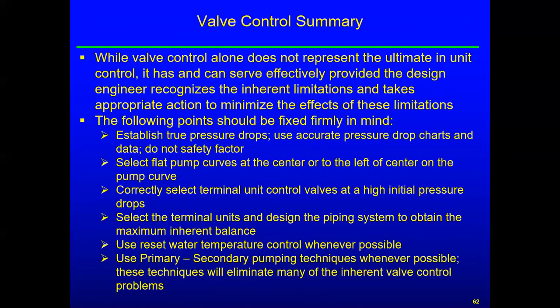To summarize control valves: while the valve alone does not represent the ultimate in unit control, it can serve effectively provided the design engineer recognizes the inherent limitations and takes appropriate action to minimize their effects. So the following points should be kept in mind. Calculate real pressure drops. Use accurate charts and data. Don't just use rules of thumb and safety factors. We want flat pump curves, especially if it's going to be a constant speed pump. And we want to select to the center or left center of the pump curve. Correctly select terminal unit control valves at a high initial pressure drop. We had some guidelines on that. Select the terminal units and design the piping to obtain the maximum inherent balance.